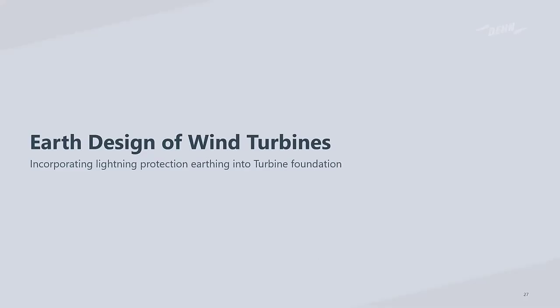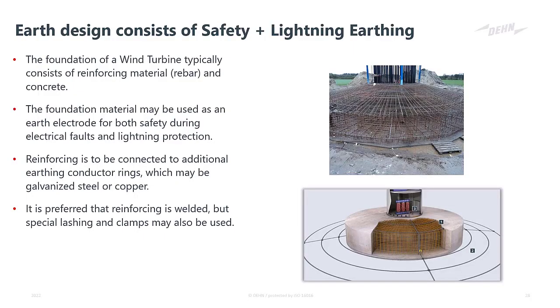Now, if we briefly move on to the earth designs for wind turbines, the earth design or the earthing system, the grounding system, is incorporated into the foundation of the turbine itself. You can see here is a typical installation of a turbine foundation. Now, the foundation consists of rebar, reinforcing material, and concrete, and this forms the majority of the earthing system. Even through concrete, concrete actually extracts moisture from the soil around it, and it becomes conductive. So concrete is also conductive in that sense.